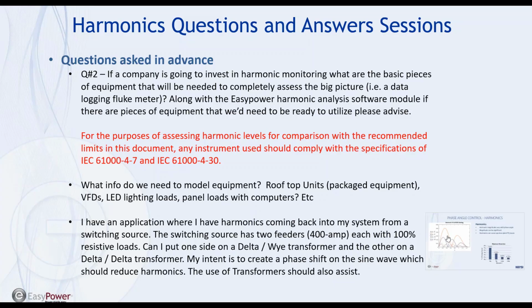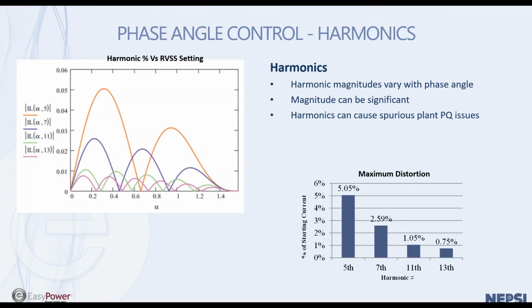I had this picture here just to show you what the harmonics look like on a phase angle control device, which I think this question relates to, maybe resistive heating. And you can see that depending upon the phase angle of operation, there are significantly different levels of harmonic current injection by that device. So a VFD drive would be similar. I think if you did a quick search on the web and looked at phase angle versus loading level for a VFD drive, you would find other types of plots like this that would show harmonic current amplitude and phase angle to change quite a bit based upon loading level.